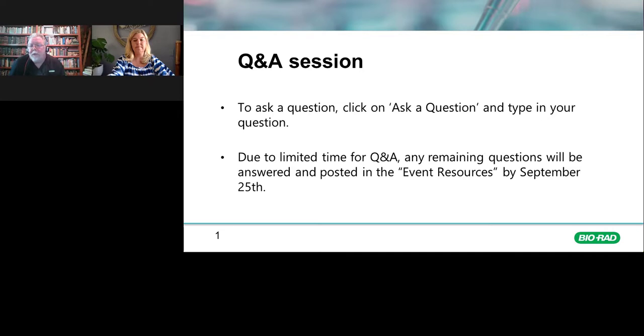The ideal scenario is that you don't release results until you've passed QC, but that is not actually the case in a lot of scenarios. That simply does not happen. And so what you have to look at then is that the design consideration that we talked about still works. You simply have to be aware that the risk goes up when you are releasing results, because your opportunity for correcting them may be diminished.